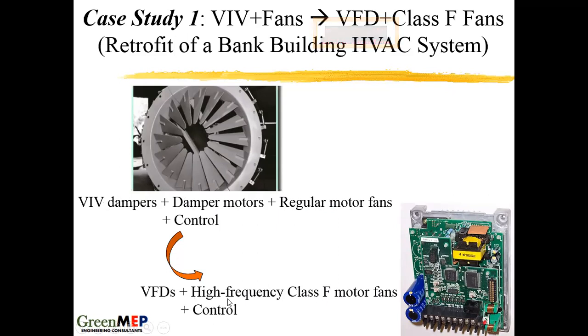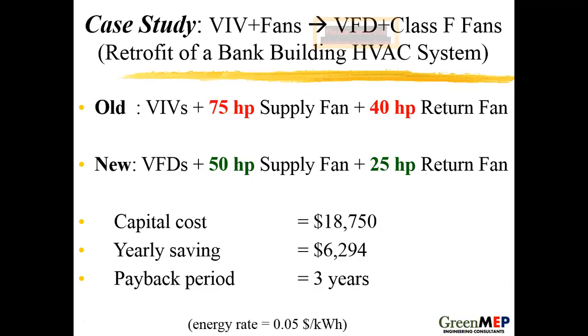Now, electronics and controls, there is some investment because you need to invest, but these things are becoming cheaper and cheaper. This way, you control the flow by adjusting the speed, and then you save power. That's right. I have only 20 minutes, so I got to move fast. In this kind of example, you go with VFD instead of constant speed drives, variable frequency drives. Not only are you saving energy, there is a 3 year payback period for the investment, right?